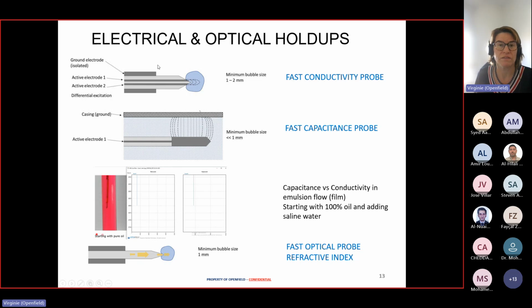For the water to be detected, it needs to be a certain size. If it's in bubble flow, we need a bubble size of 1 to 2 millimeter, and it's related to the spacing of the electrodes. So when we have a high rate, whether it's emulsion, oil emulsion, or mist flow for gas, a high gas rate, these water droplets will be below that size. They're going to be sheared, and they can easily be below 1 millimeter. And this is why we developed a capacitance probe.